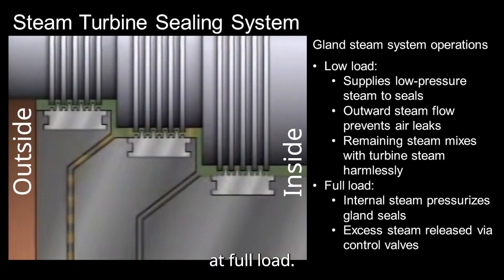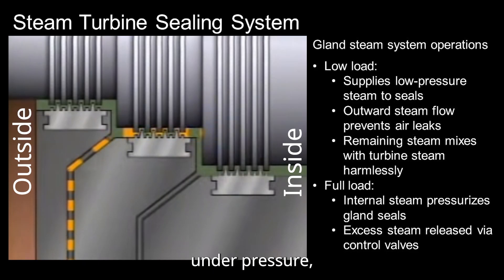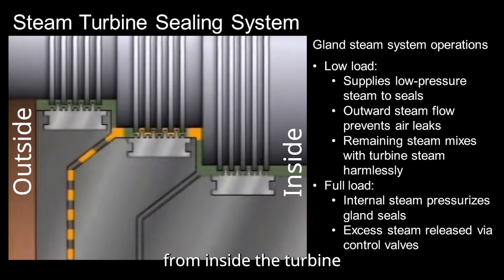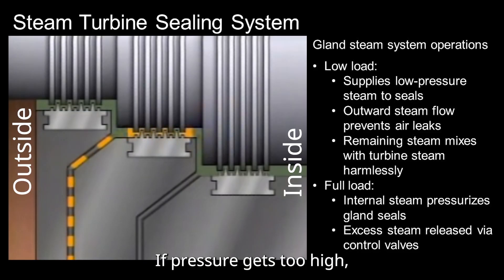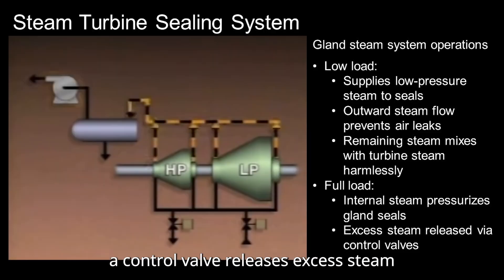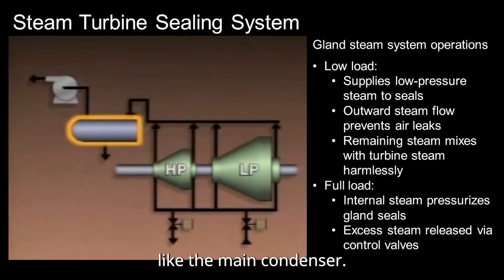At full load, when most of the turbine operates under pressure, steam from inside the turbine pressurizes the gland seals. If pressure gets too high, a control valve releases excess steam to a low-pressure area, like the main condenser.